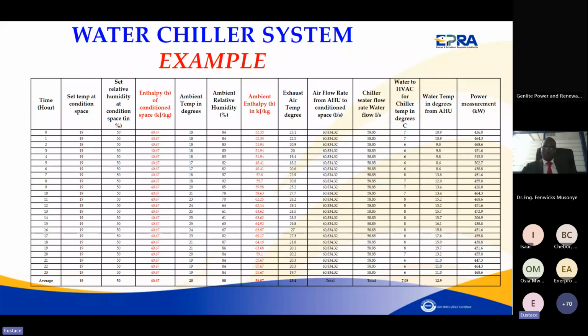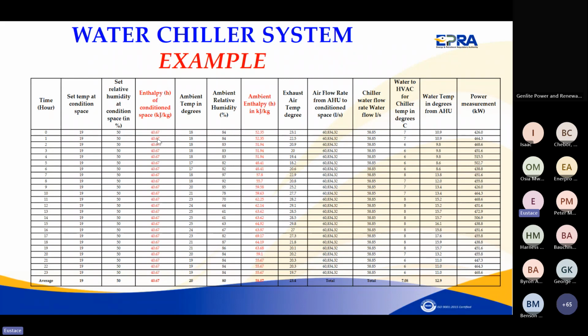Oh, thanks very much. So I'm saying that those are the parameters you need to measure. And enthalpies are calculated values, which will be very important. Especially when you are dealing with the ambient temperature, you can calculate the energy required to change that air from, say, 18 degrees and 84% relative humidity to 19 degrees and 50%. You need to remove some water. So there is both sensible cooling and latent cooling. In this case, you do not want to use the change in temperatures directly.